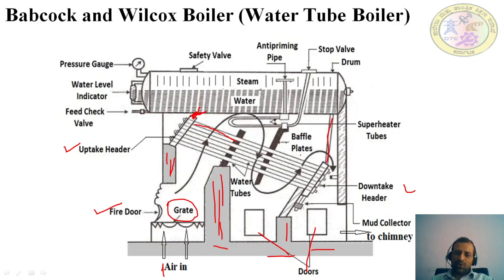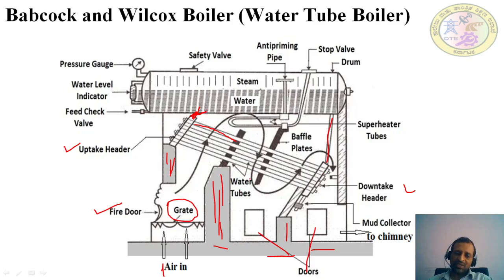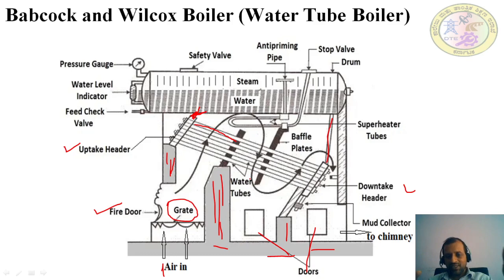Baffle plates are placed here to change the direction of the flow of the flue gases. When the flue gases flow in a zigzag manner, the time they spend in contact with the water tubes is longer, resulting in better heat transfer. To make the flue gases flow in this zigzag manner, baffle plates are placed in between.